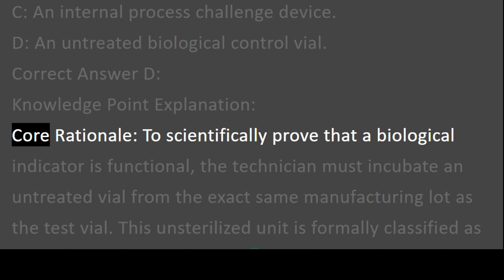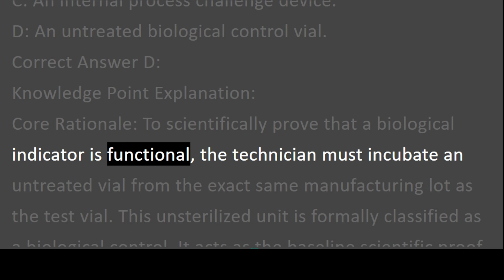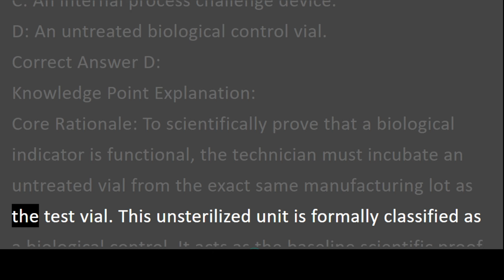Correct answer D. Knowledge point explanation. Core rationale. To scientifically prove that a biological indicator is functional, the technician must incubate an untreated vial from the exact same manufacturing lot as the test vial. This unsterilized unit is formally classified as a biological control. It acts as the baseline scientific proof that the microscopic spores were alive and viable before the actual test vial was subjected to the lethal autoclave cycle.